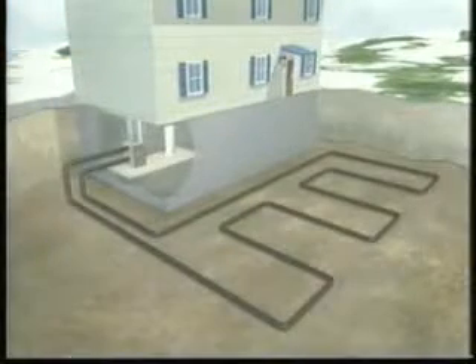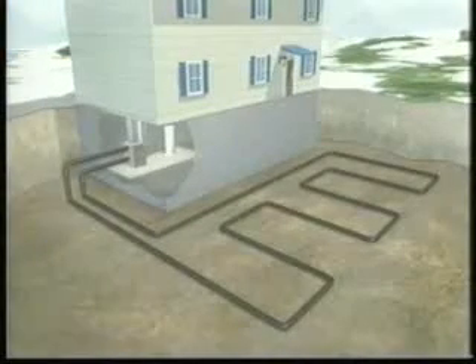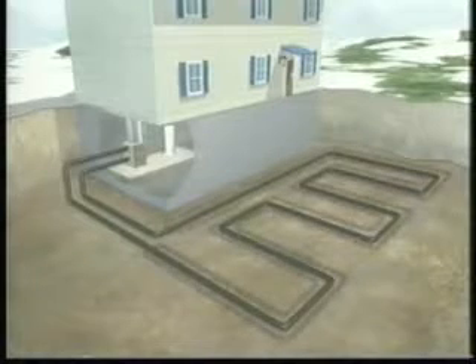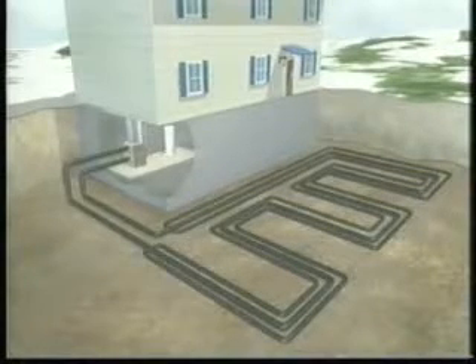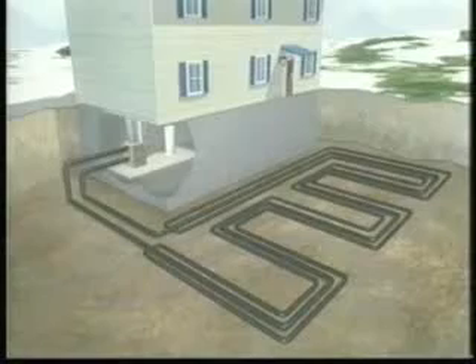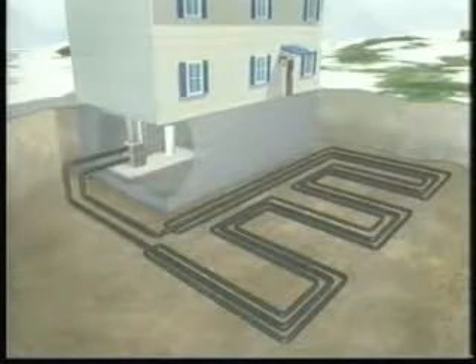In some installations, the pipes of a closed loop system can be placed in a horizontal trench dug below the frost line. The number of pipes in each trench and the number of trenches needed will vary depending on the size of the geo-exchange system being installed and the type of soil found in the area.